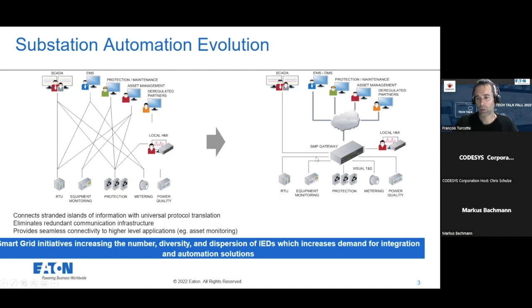So what we offer is a box that allows them to separate their network and just restrict access to those IEDs communicating directly in the substation. So the SMP gateway can provide that layer of security where people will just need to configure it and have a single point of access to the remote field. So we provide a firewall. There are multiple different things that we offer in the same box.